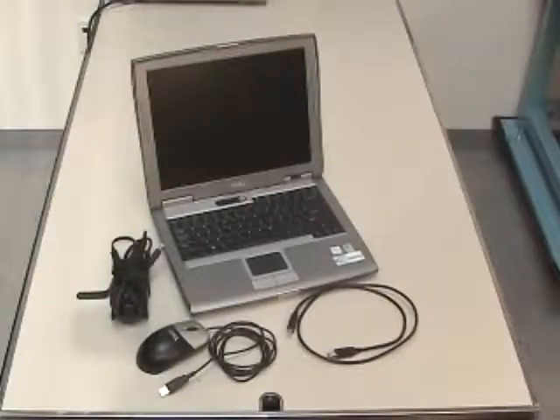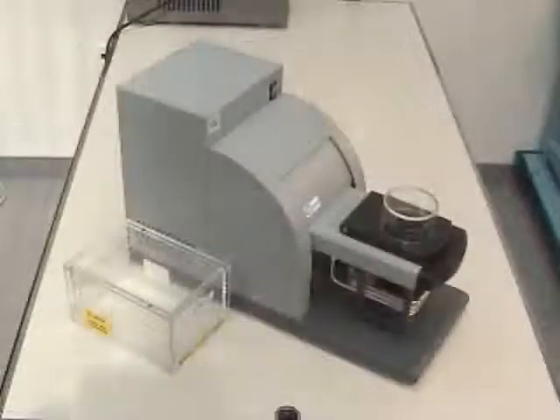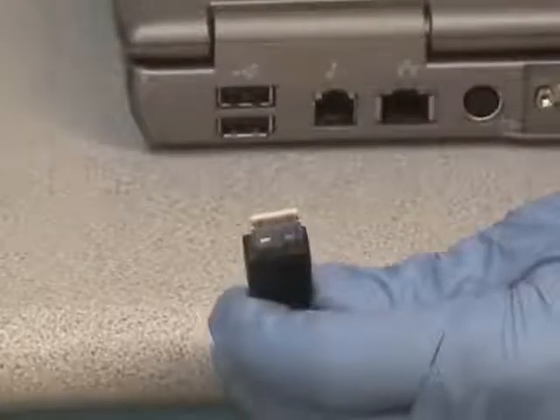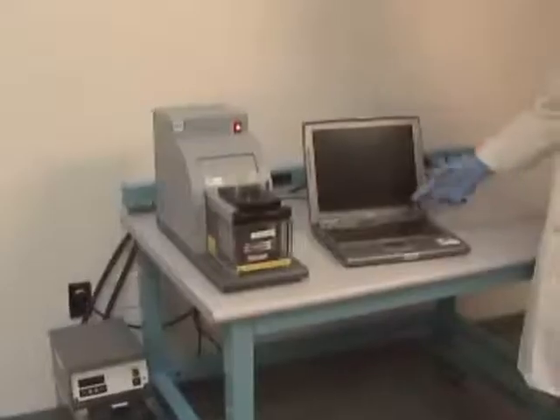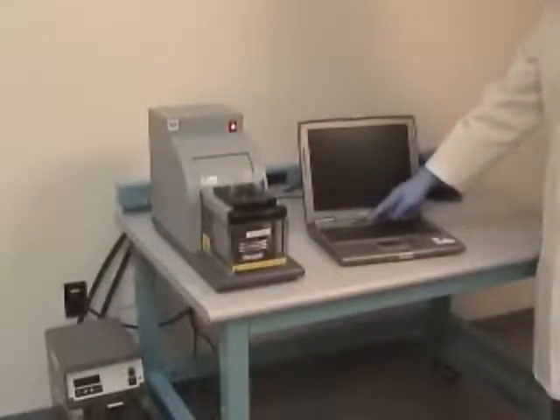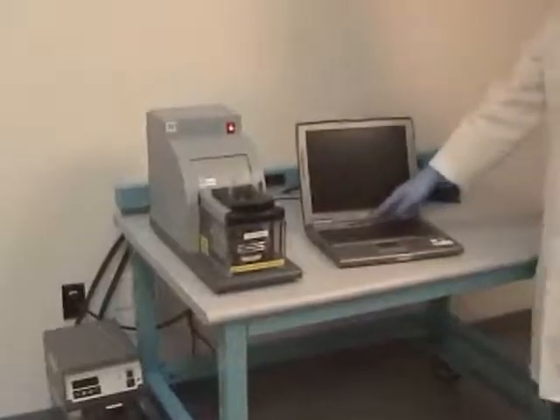Next, connect the computer to the instrument using the USB cable, wide end to the computer, square end to the S2. Plug in the power cord at the back of the instrument and turn the S2 on. The switch will light. Now plug the AC adapter into the laptop and start the computer. The software is already loaded on the laptop. If you are supplying your own computer, see the instructions in Appendix B of the user manual. Make sure that the S2 instrument is turned on first, and then the computer.